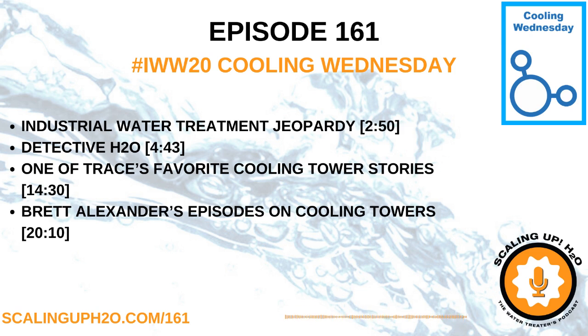Moving on to the cooling tower, he noted a fine white foam covering parts of the sump's water surface. Some of it got caught up and flew out the top fan as he took a peek inside the cooling tower plenum area. Detective H2O then led Misty back to the sodium hypochlorite feed pump, which he swiftly turned off.